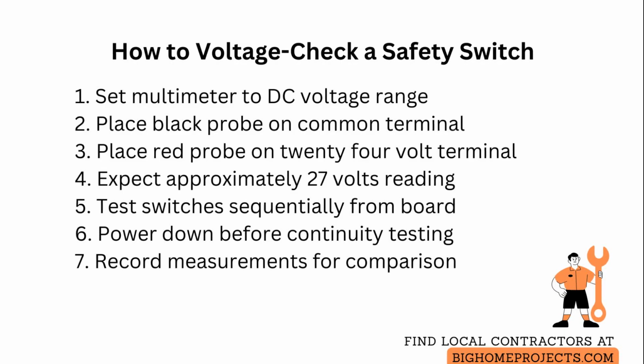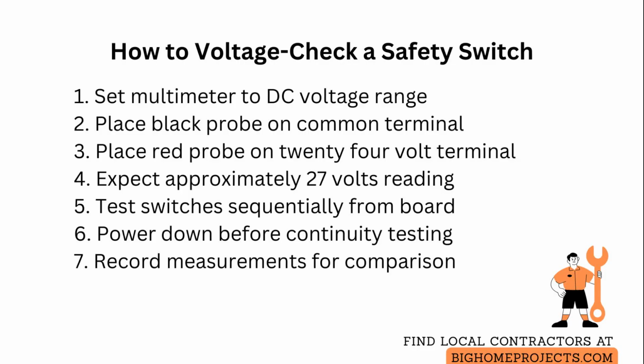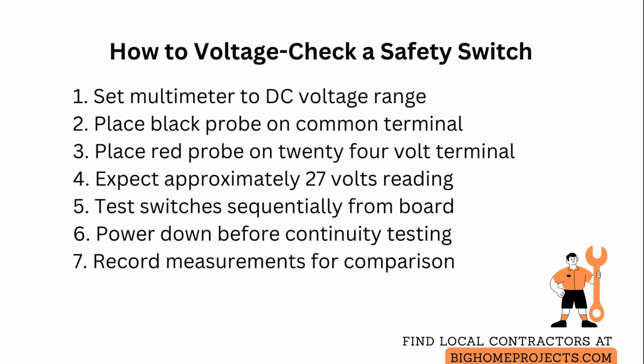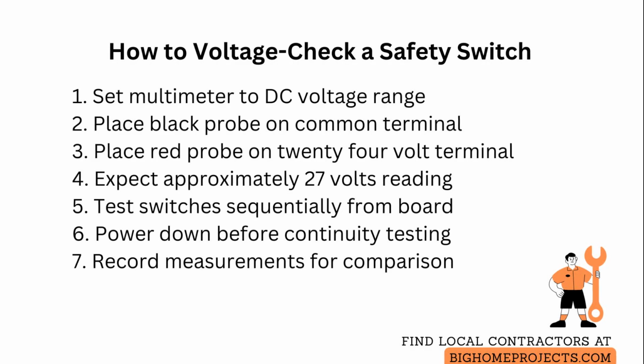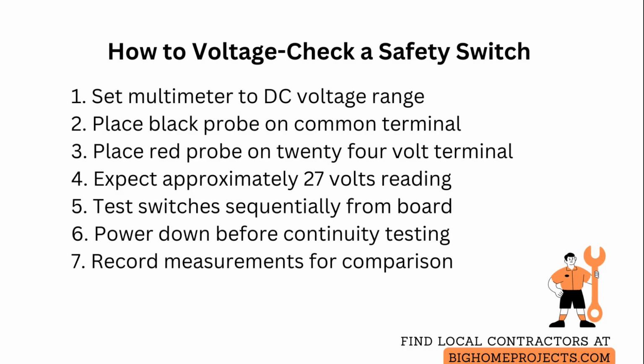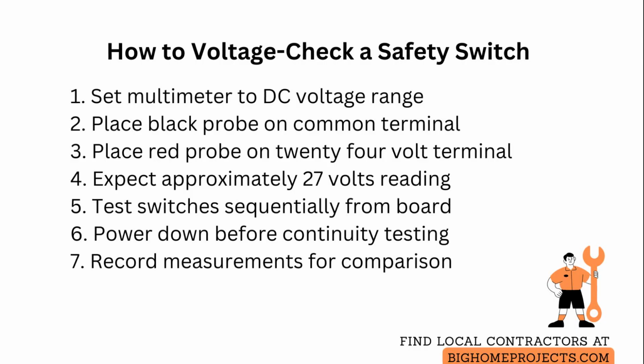that point. If you do not read voltage at a particular switch location, you can isolate whether the fault is before or after that switch by testing at the control board and then at each switch in sequence toward the load. For switches that are mechanical, also test continuity with the multimeter set to resistance or continuity only after powering the circuit down and disconnecting power to avoid damage.